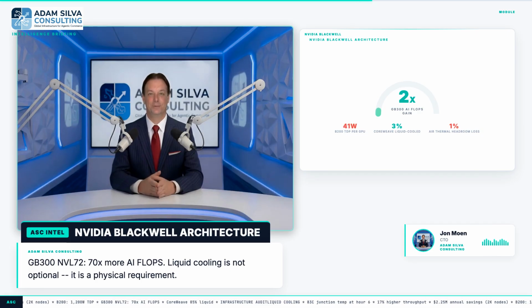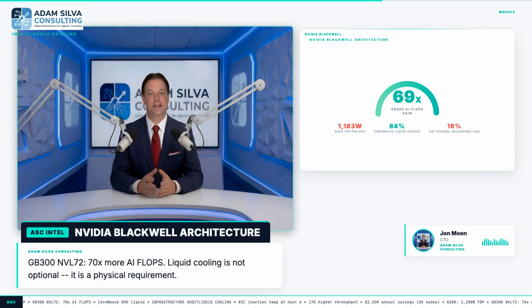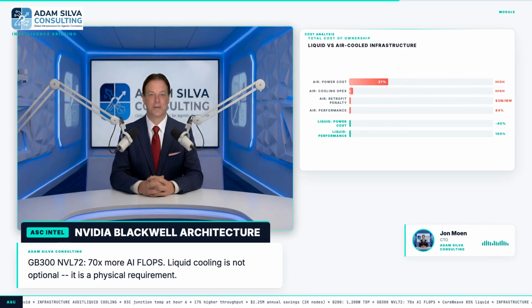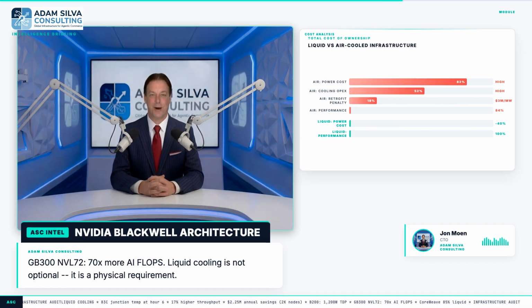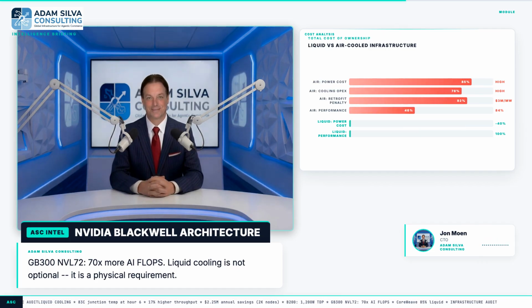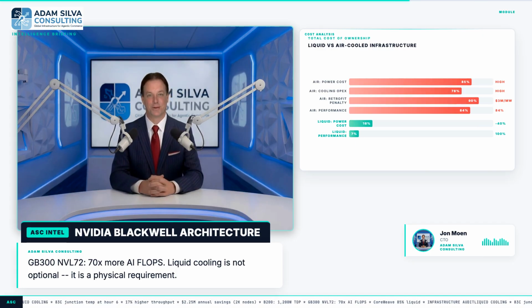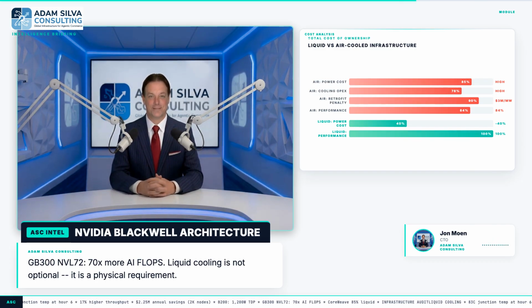The NVIDIA B200 Blackwell puts the liquid cooling conversation beyond debate. At 1200 watts TDP per GPU in liquid-cooled mode, air cooling means accepting a 200-watt TDP reduction per GPU, 16% less thermal headroom. You are paying for the full performance of the B200 and air cooling your way to 84%. The GB300 NVL72 takes this further. 72 Blackwell GPUs in a single rack-scale unit, 70 times more AI flops than the previous generation. Liquid cooling is not an option at this configuration. It is a physical requirement. The power density exceeds what any air cooling system can handle.